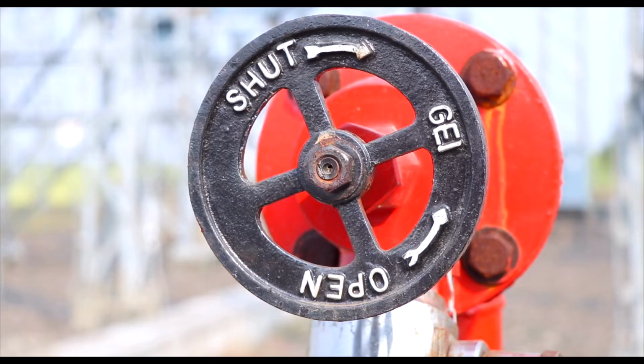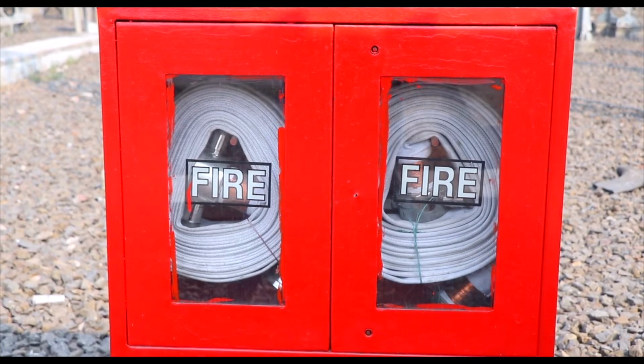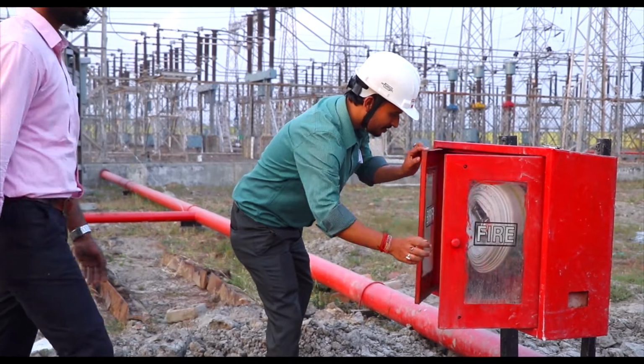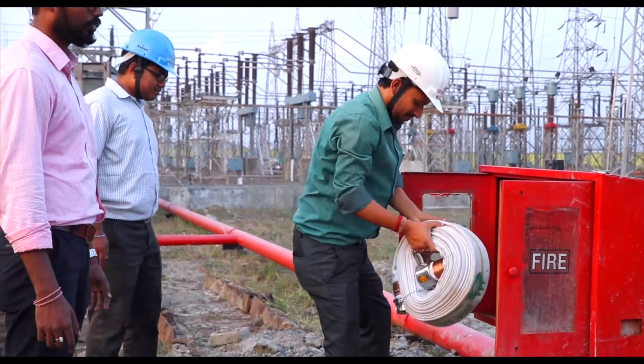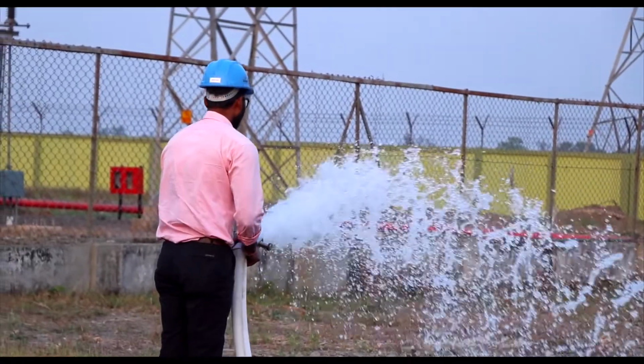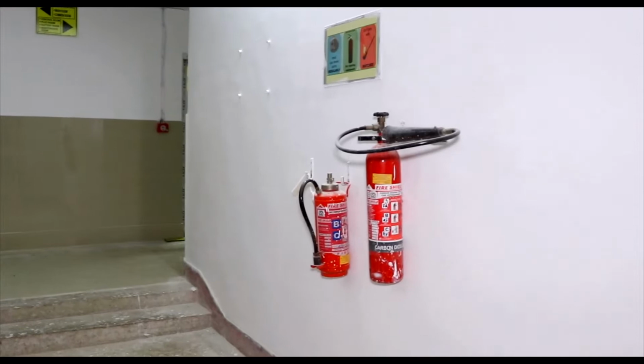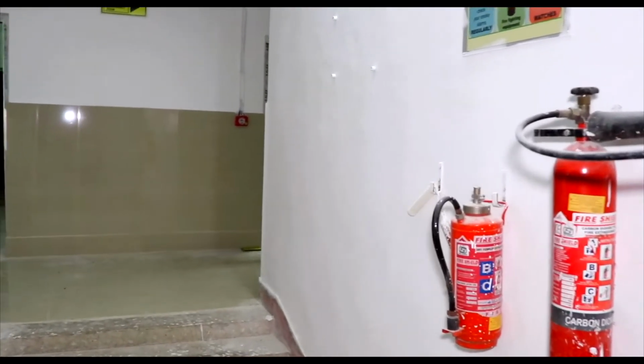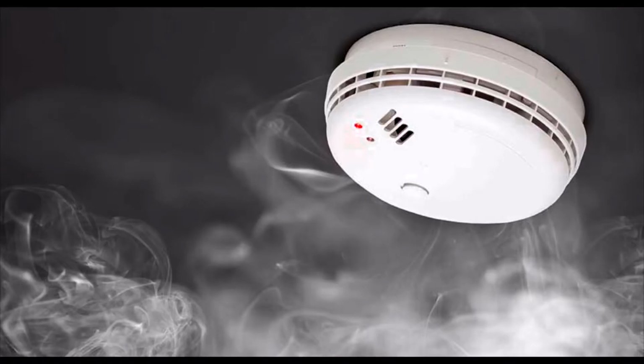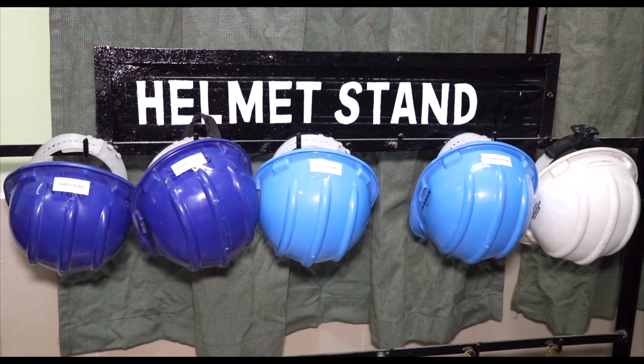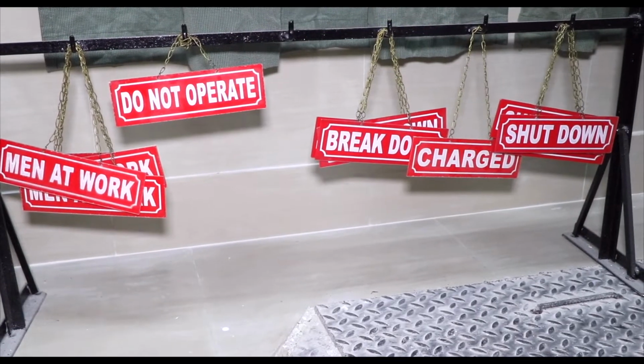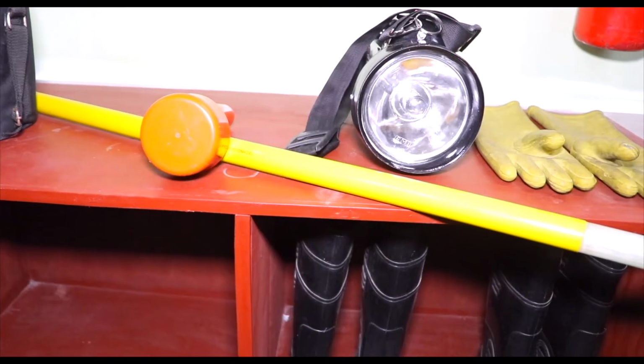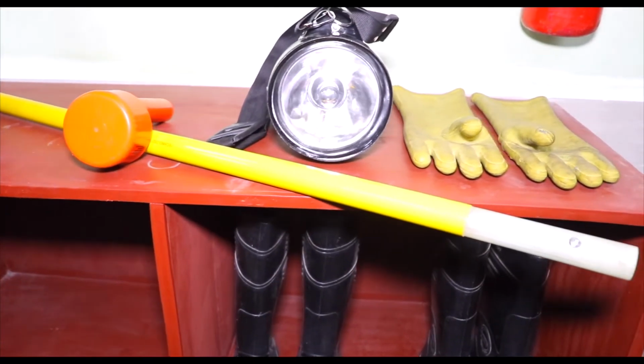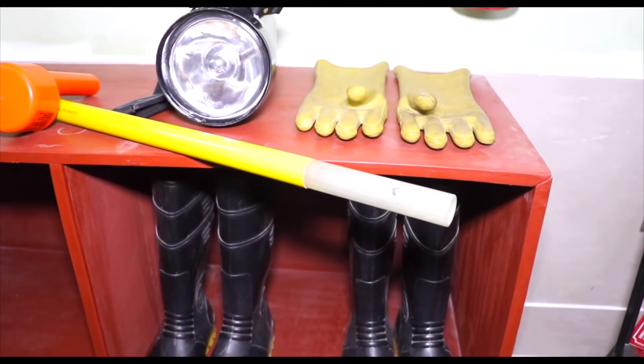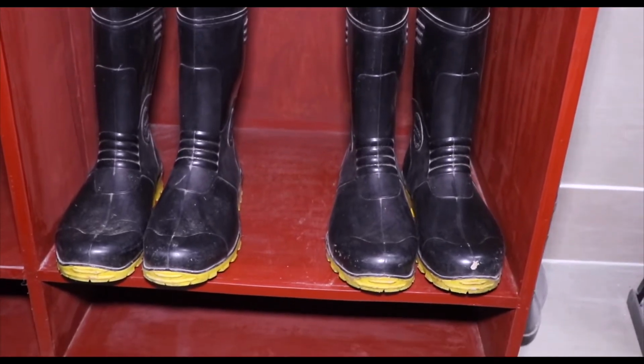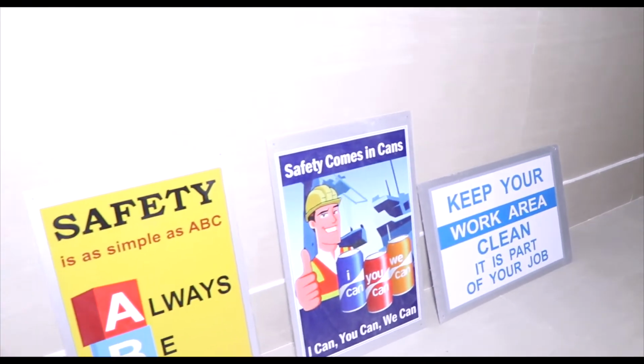The switchyard is surrounded with a reliable fire hydrant system installed with a 40 HP pump motor set and backup DG set ready to deliver 96 cubic meters per hour, and also has fire extinguishers of dry chemical, carbon dioxide, foam type and sand buckets of sufficient number and an in-house smoke detector system. Individual safety is maintained with proper guidelines through various safety boards along with safety equipment like helmet, hand gloves, safety shoes, gumboot, raincoat, safety ladder, searchlight, safety belt and HV detector. Proper first aid is maintained for medical emergency.